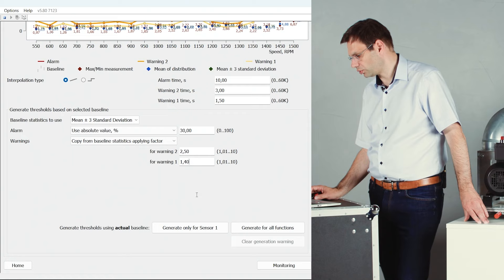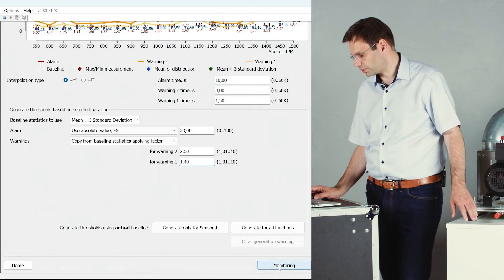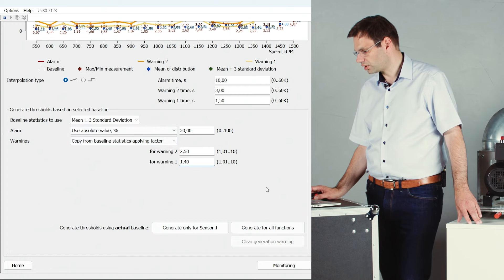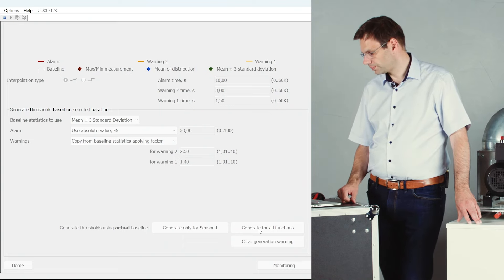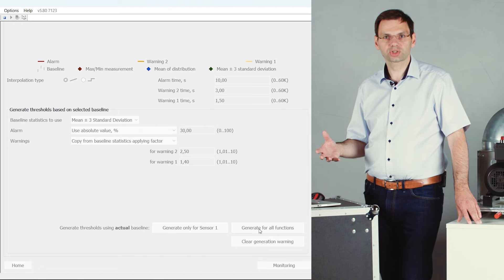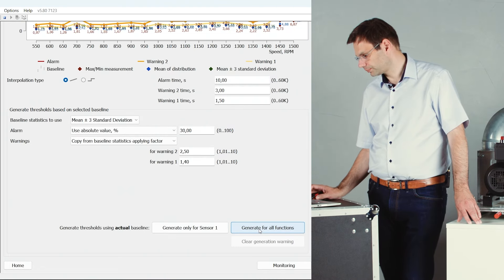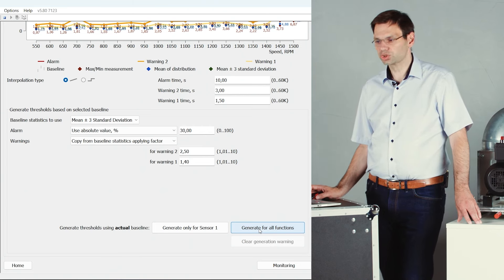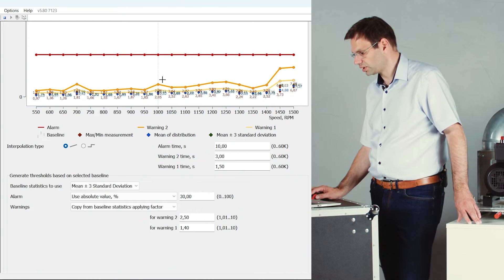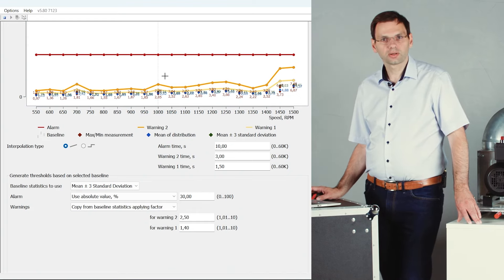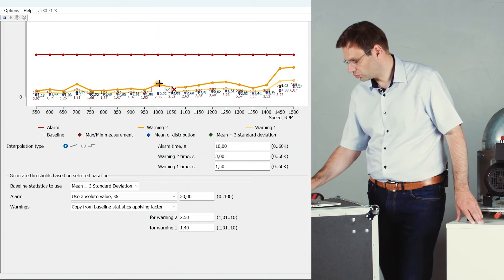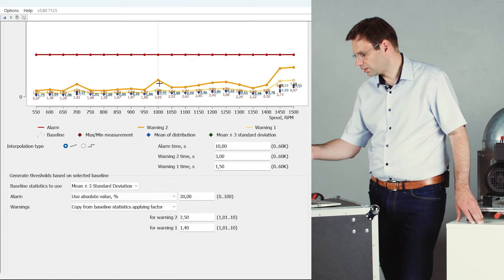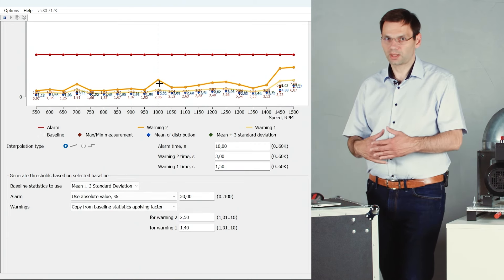If you have more experience, you can make all these adjustments — the system is flexible. Once you have configured everything and are happy with the results, you can generate the thresholds either for one specific function or for all functions. You can always come back and edit a threshold, and you can also edit an individual point — for example, if you have a resonance or another condition, you can manually put in a new baseline value and the threshold will change accordingly.